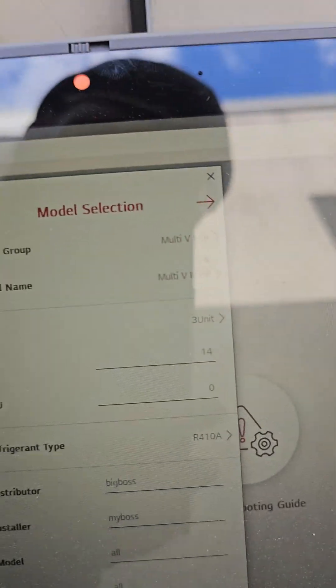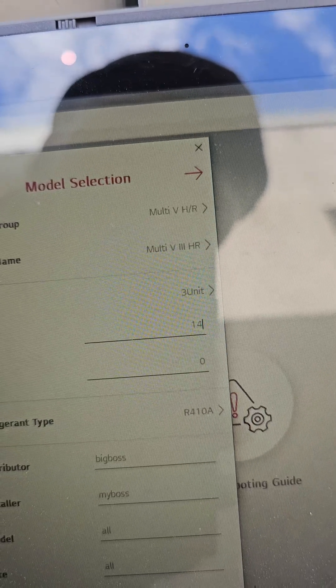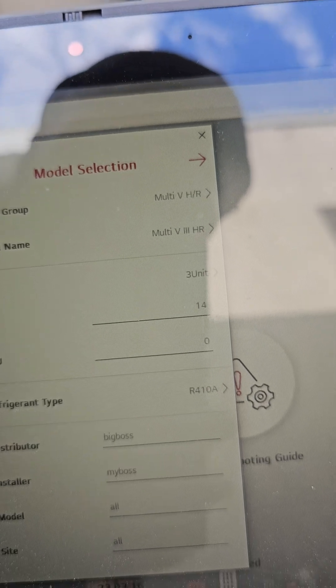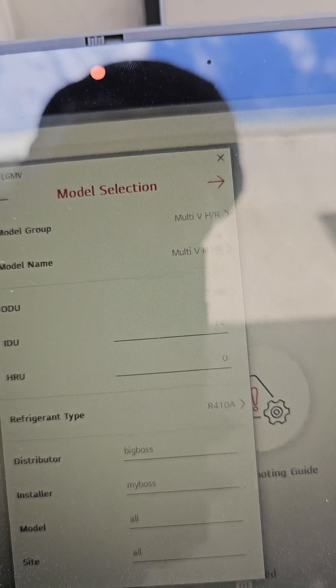Okay, what we have here: we've got Multi-V H/R up top. Multi-V III HR. And outdoor, we've got three units — that's correct. Indoors, 14. However, it didn't select my HR for me, so I've got five HRs. Just going to see this case — five.